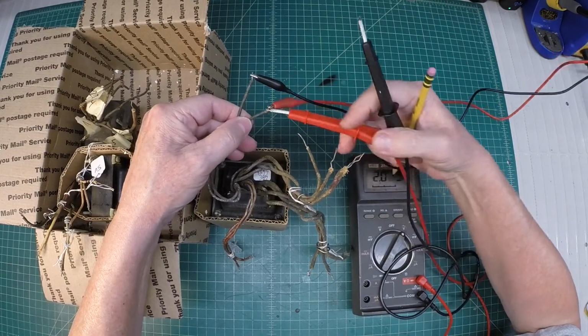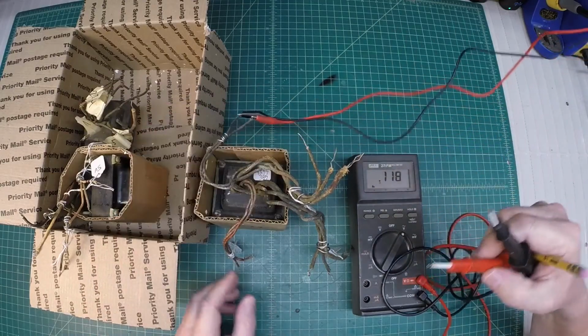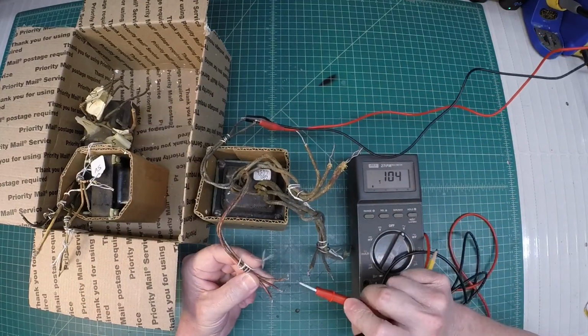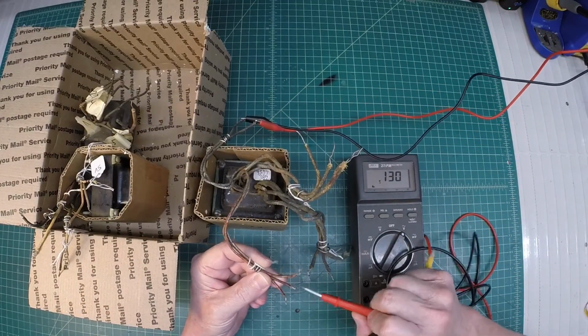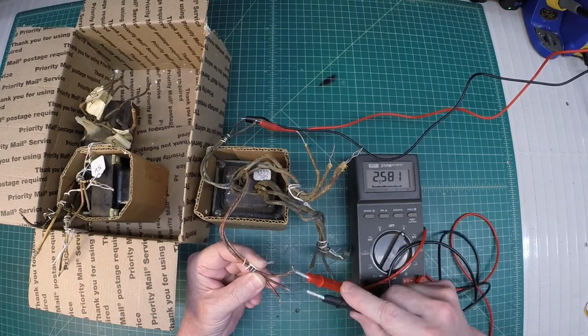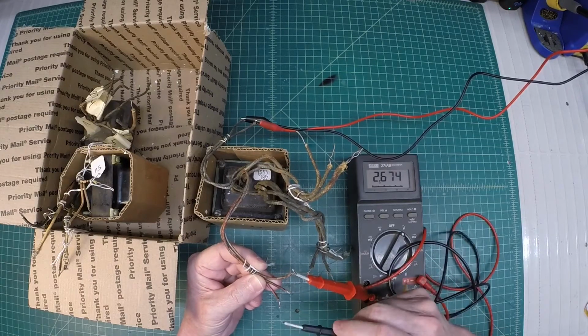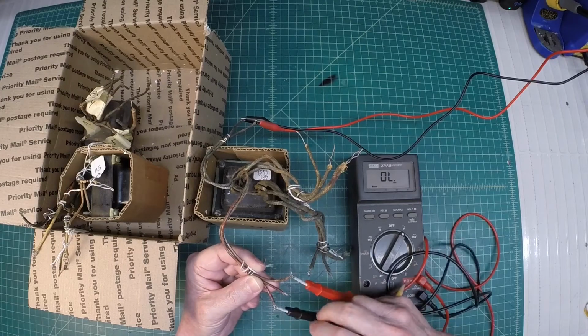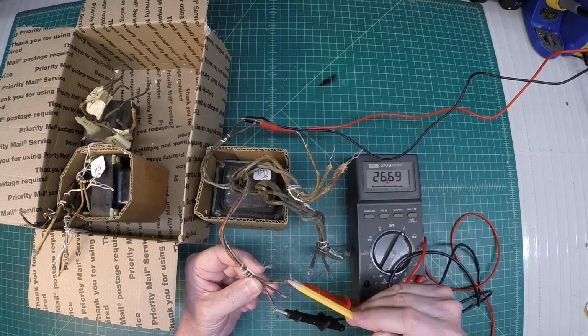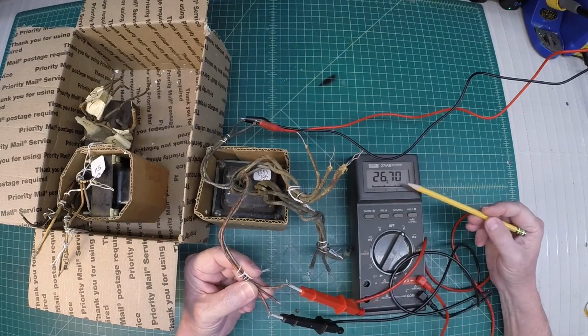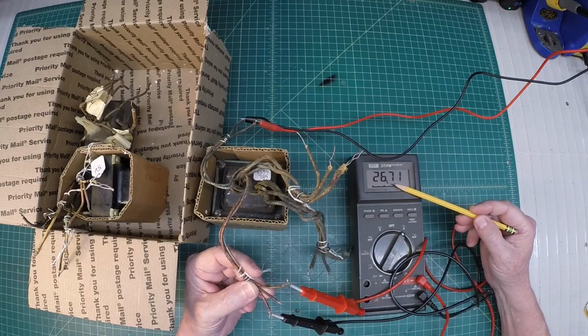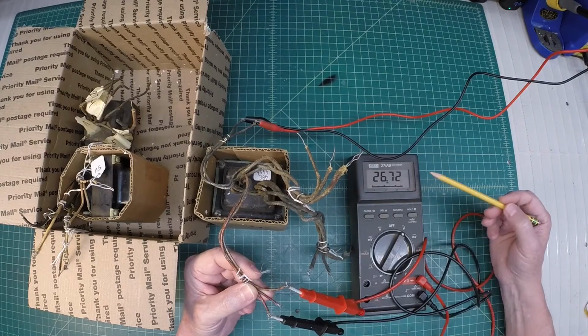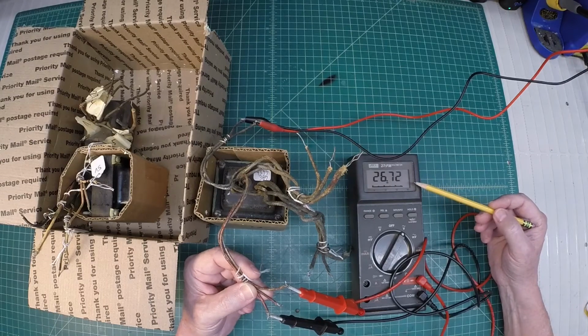I'll take the leads loose here and apply them across the high voltage winding. Again, the center tap being here, I'm going all the way across, which would be the plate to plate connection points. You can see my reference of 26.7 — let's document that number.